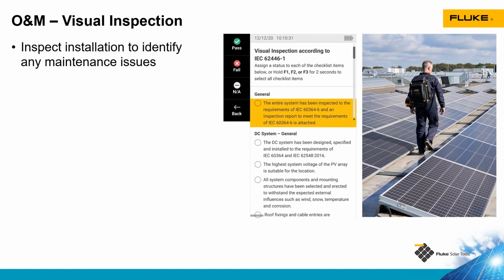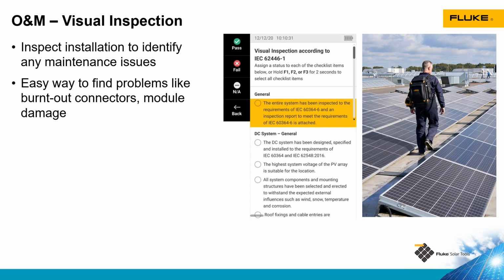During operations and maintenance, a visual inspection is usually the first thing we do when we're doing any kind of maintenance or troubleshooting on the system. So walking around, see if we can find any issues. We're looking for things like burnt out connections between modules, wiring issues, damage to modules like shattered glass or damaged cells that are burnt out. Lots of different things we can see when we're walking around doing a visual inspection.